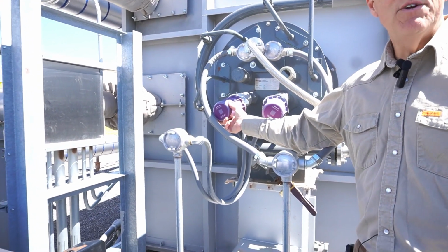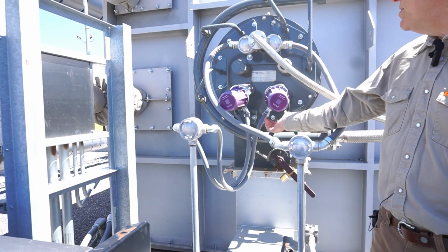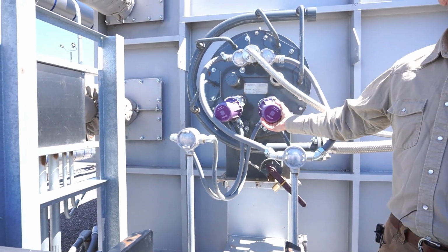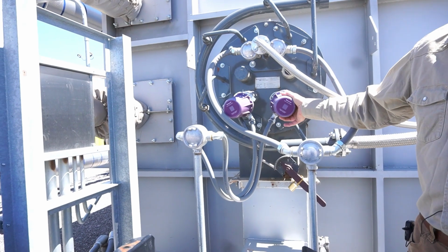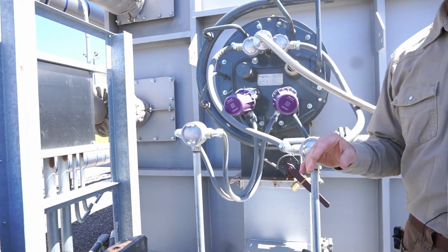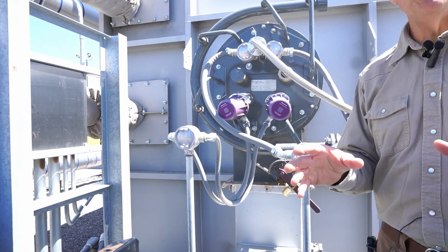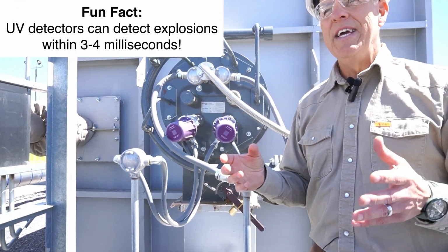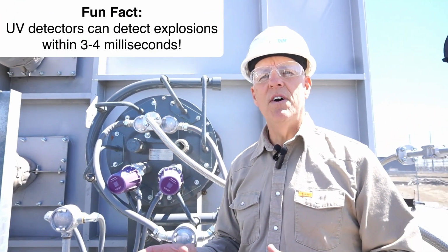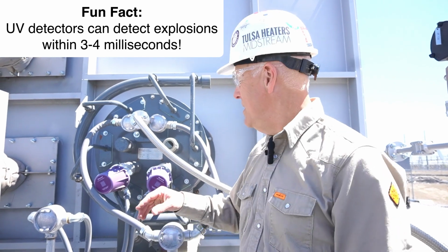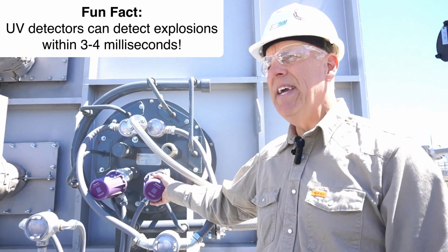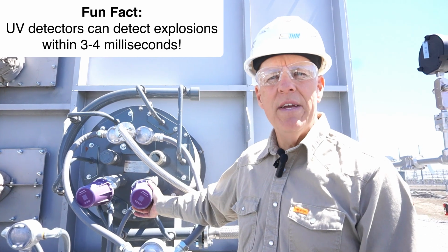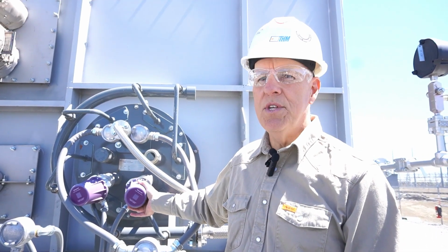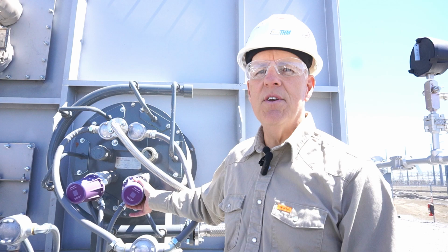These are flame scanners, ultraviolet or UV flame scanners. I think Honeywell calls them purple peepers, if you can believe that. And they're constantly looking for flame, because if flame is present, that means, hey, things are good. If flame is not present when the gas is on, that's not good. And so what these scanners do is if they are looking for flame and there should be flame, but they don't see flame, then it turns the gas off.